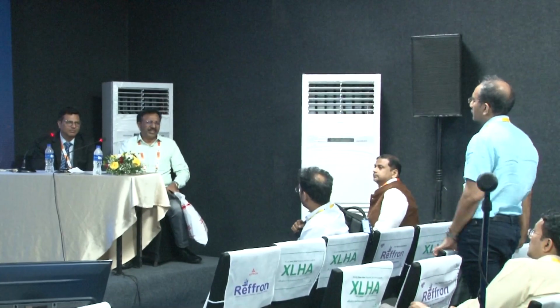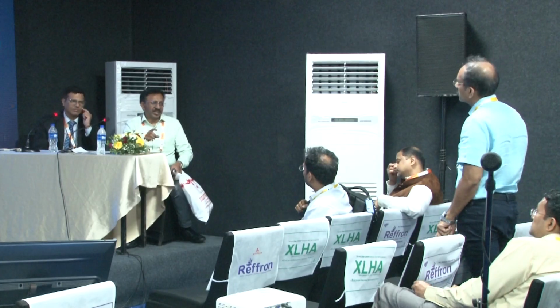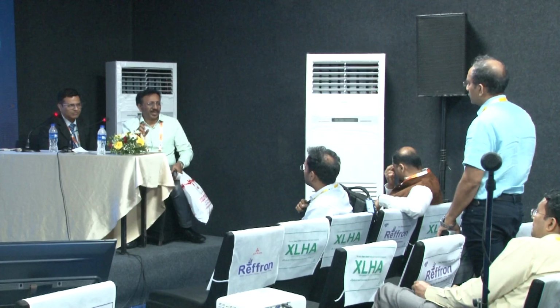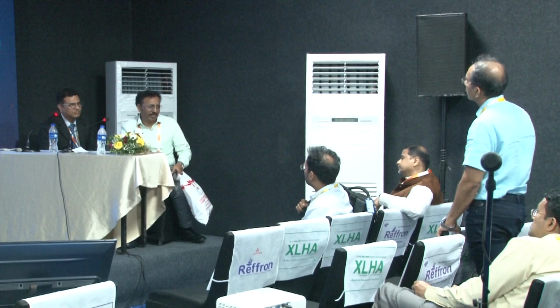There is something called the proximal filter, which is near the edge, that is at the plenum. If you don't have a filter at the plenum, then the height can be reduced. Some engineering modification can be done, but we have to do a proper validation, and not only biological validation by the engineers. We have to check the pressure, the flow velocity, the air exchange, and check the laminar flow. All of this has to be checked by the engineering people. It is their duty. Our duty is to ensure that it is being done.